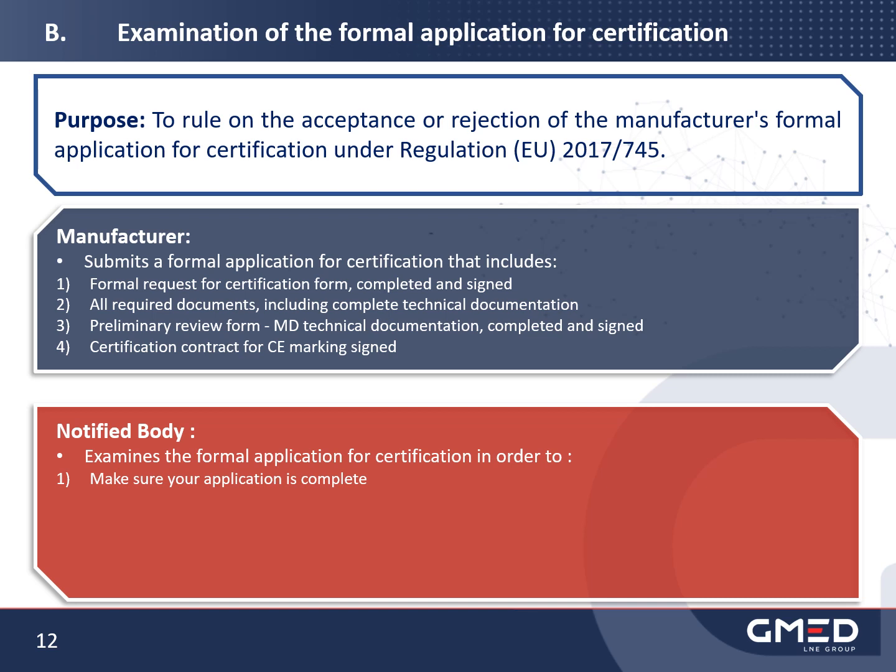And secondly, to ensure that GMED has at its disposal all of the documents and data required to carry out conformity assessment activities under the regulation in the best possible conditions, such as complete technical documentation and the company's quality manual. Please note that during this verification, GMED does not assess the conformity of documents and information transmitted by the manufacturer to regulatory requirements. Compliance with regulatory requirements is assessed as part of the appropriate conformity assessment activities, mainly the assessment of technical documentation and the audit of the quality management system.